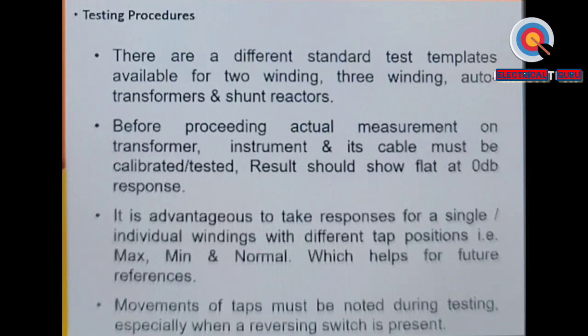It is advantageous to take responses from a single individual winding with different tap positions, that is maximum, minimum, and normal tap, which helps for future reference. So if we are testing a transformer which has a tap changer, whether OLTC or off-circuit, it is advisable that it should be tested at different taps also, preferably maximum, minimum, and normal. Maybe you can take one or two additional points in between, but these are the three extreme points for which the graph should be obtained. So it serves as a reference graph for the future.